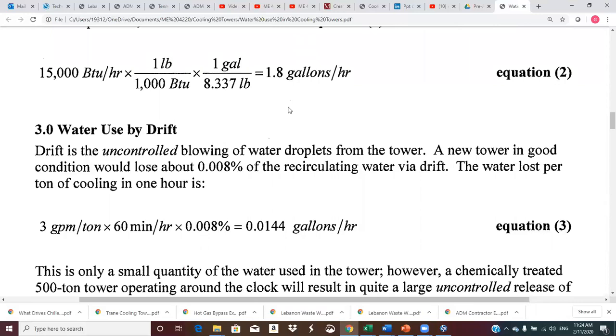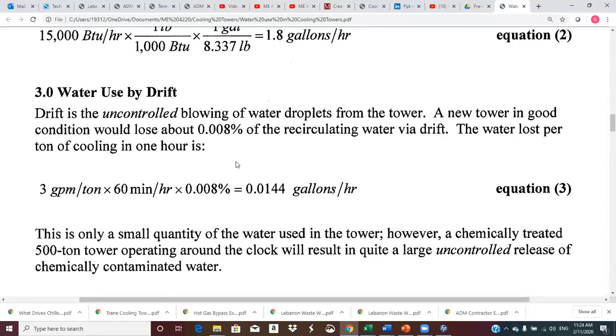I mean, like on this homework, if we're doing a 300 ton chiller, then it's pretty easy to figure out roughly how much water is going to be evaporated in a month if it operates at full. So you have to assume what percent load it's going to operate at. Okay. Moving on, water used by drift.